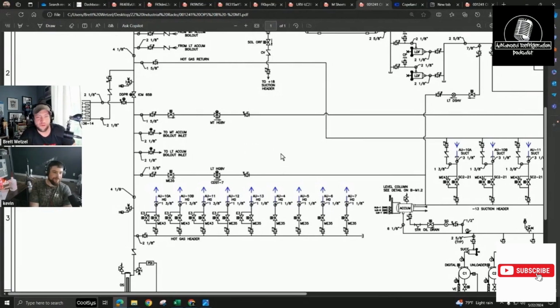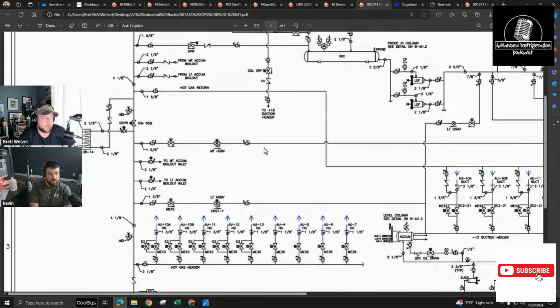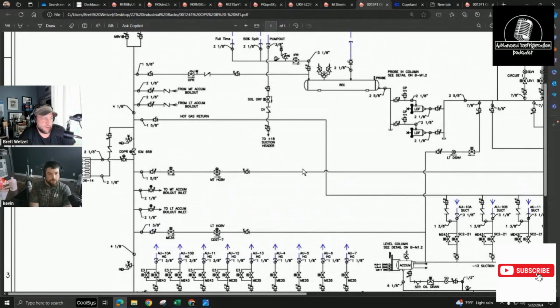The rules are out now - it can only be a GWP of 150 for anything less than 150 pounds, and it has to be installed before 2027. But yeah, you can still use HFOs out there, you just need to get them installed before 2027.